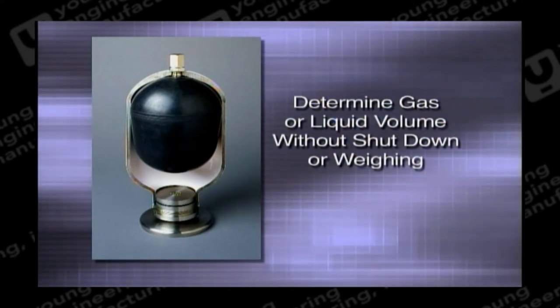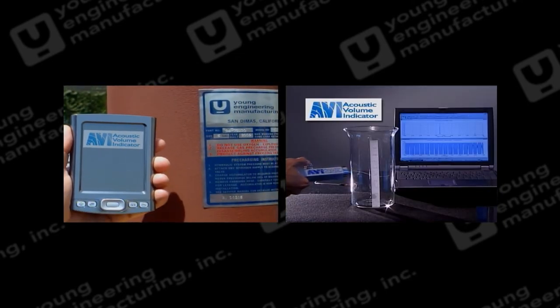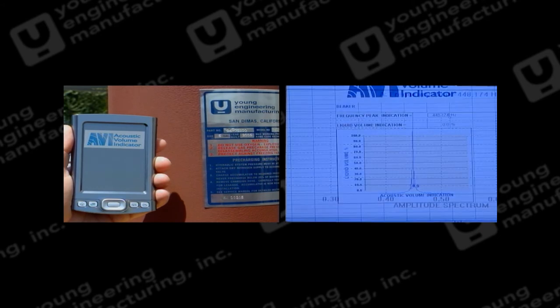Young Engineering Manufacturing holds two patents on its Acoustic Volume Indicator, or AVI, technology. A key feature of this technology is it enables somebody to measure the volume of a fluid within a tank in a non-invasive manner. The handheld system is operated directly at the location using an impactor to initiate the reading of the tank. A transducer will pick up this frequency and relay it to the handheld device. Every tank has a resonant, or normal, frequency.